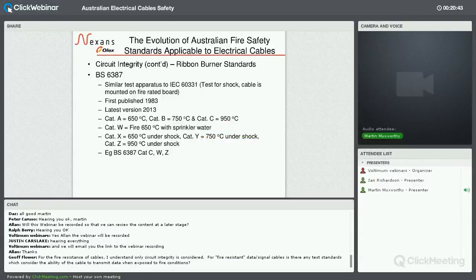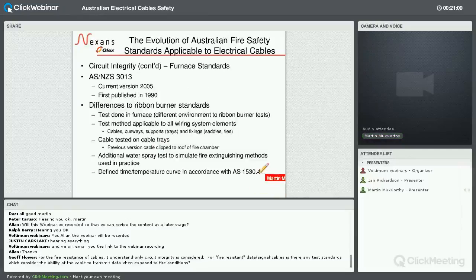And then this standard also has the fire with shock at the same 3 temperatures, and you might see logs of fire-rated cables, and they might say they comply with BS6387 category CWZ. So that just means that they've been tested to 950 degrees for fire alone, fire at 650 with sprinkler, and then fire with shock at 950 degrees, for example.